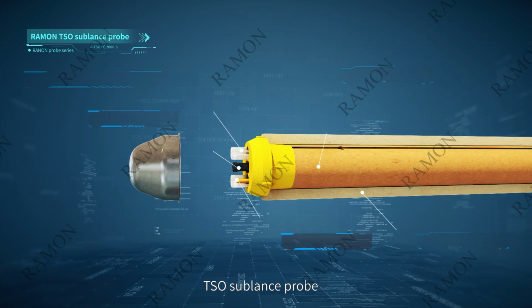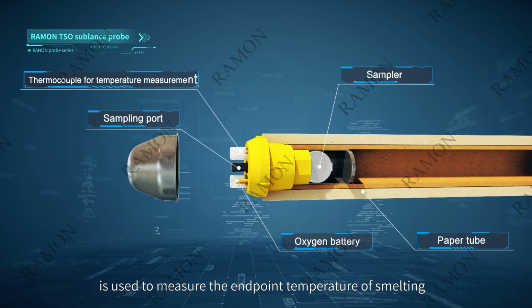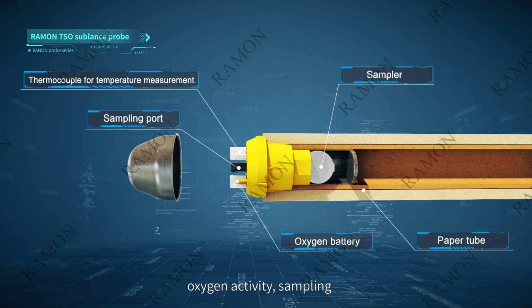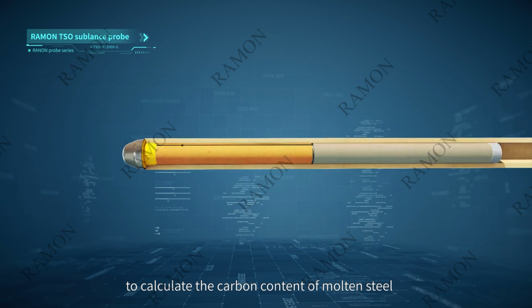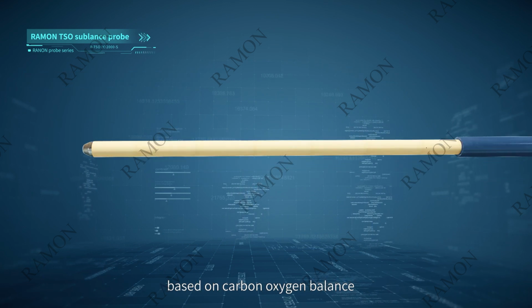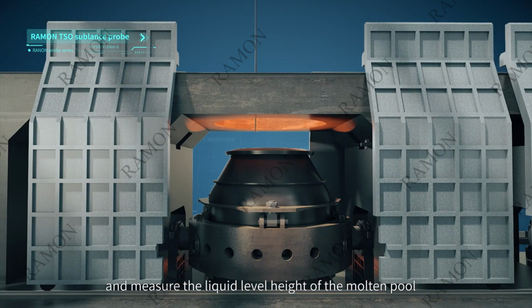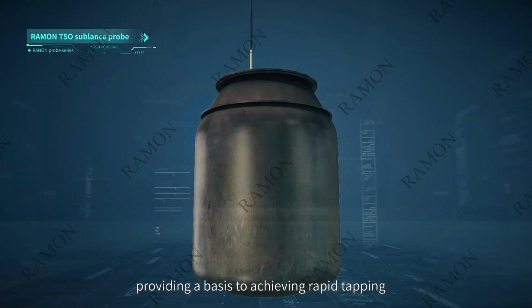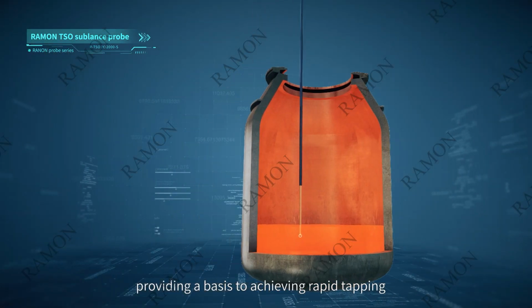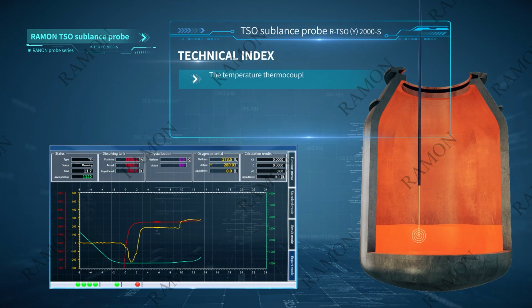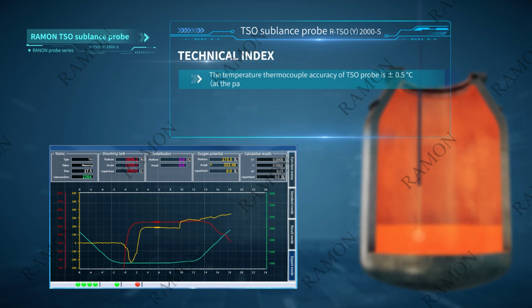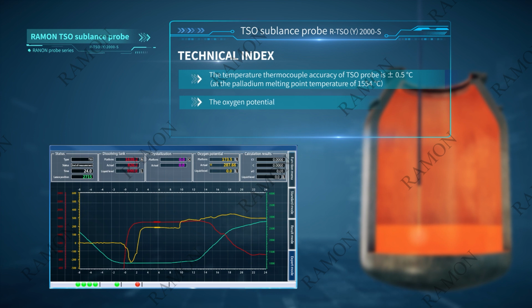TSO sublance probe is used to measure the endpoint temperature of smelting and oxygen activity, and for sampling, to calculate the carbon content of molten steel based on carbon-oxygen balance, and to measure the liquid level height of the molten pool, providing a basis for achieving rapid tapping. The temperature thermocouple accuracy of the TSO probe is plus minus 0.5 degrees Celsius. The oxygen potential accuracy is plus minus 3 mV. The success measurement rate is larger than 98%.